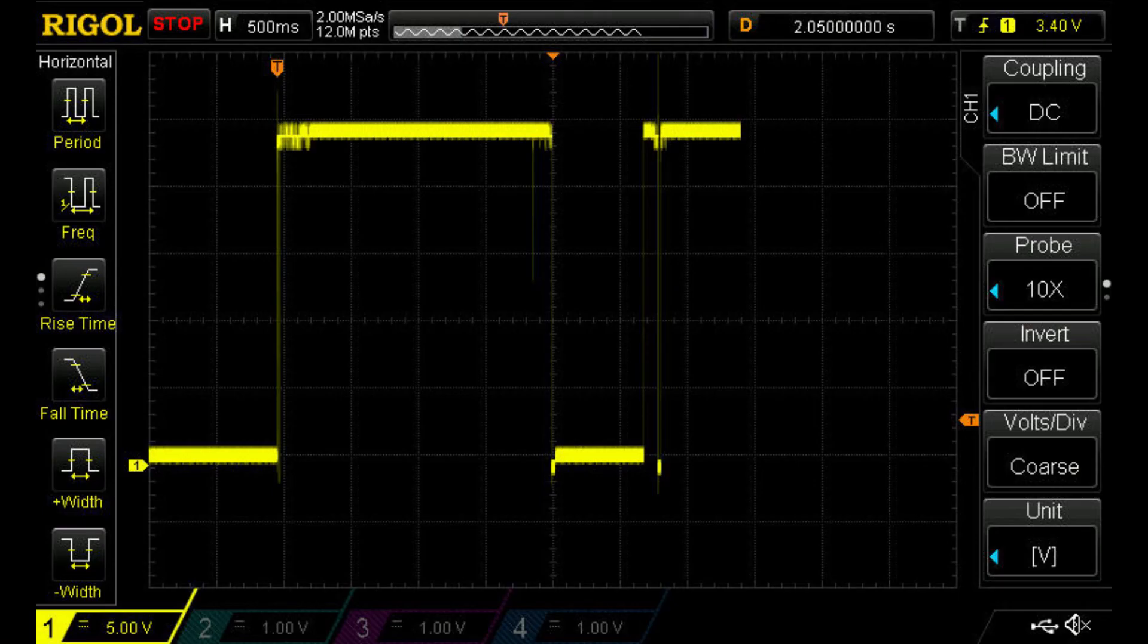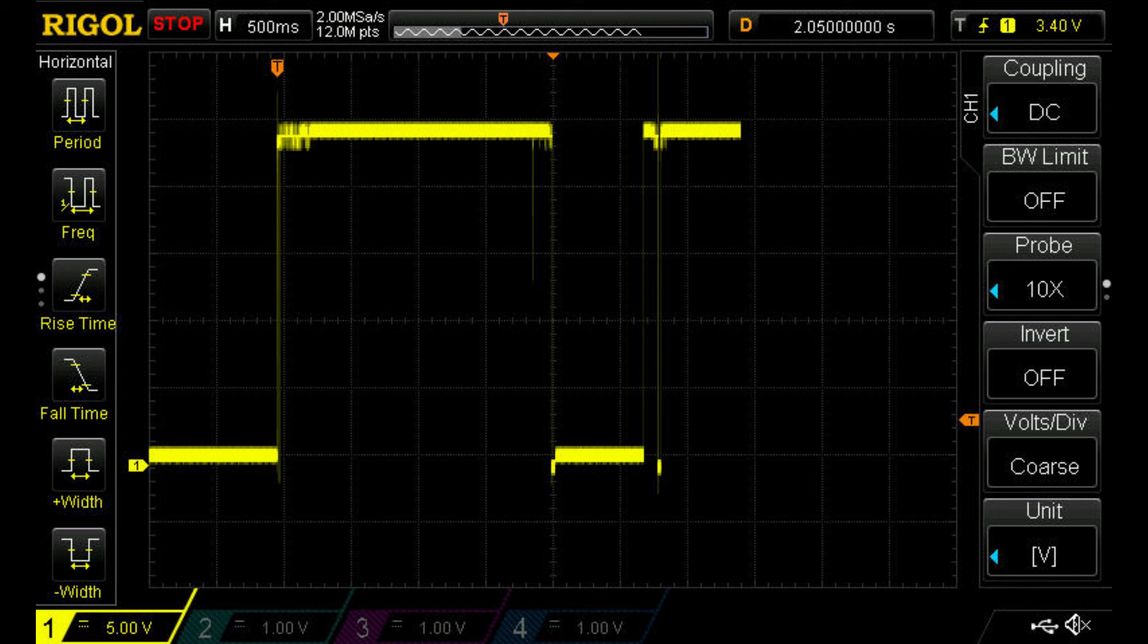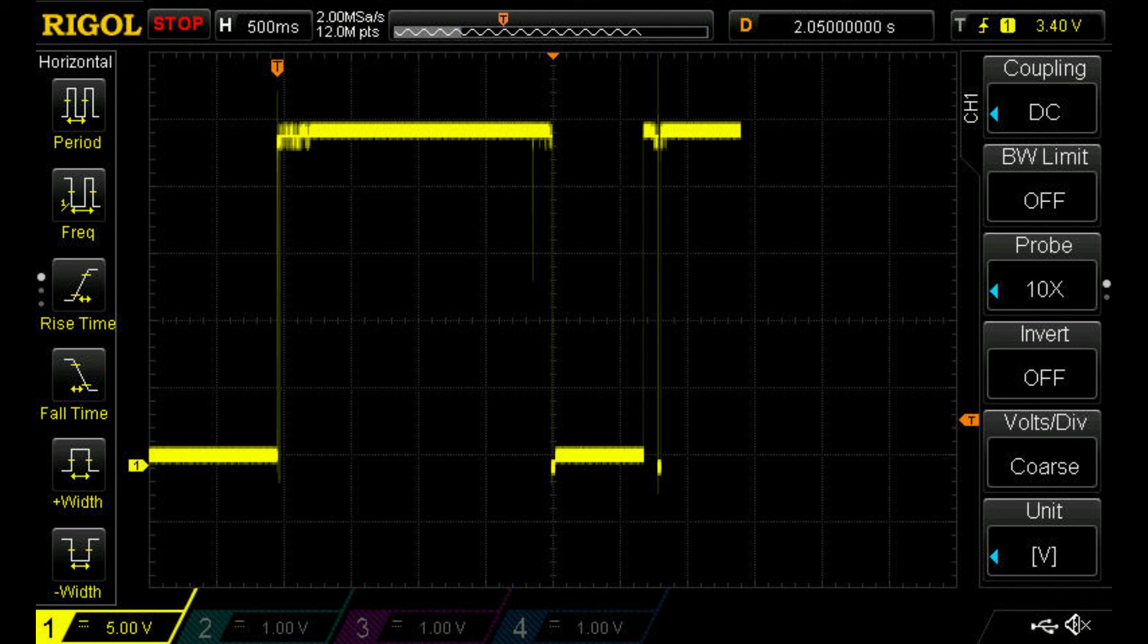Now I will add a diode to see how the signal changes. As you can see, the negative voltage has gone because the diode is acting as a clipping diode. If the diode was not present, this would have damaged the circuit, especially if driven by a transistor. Normally we have variable speed drives which have transistor outputs, and sometimes PLC output modules are based on transistors. So be sure to have diodes on the relays.